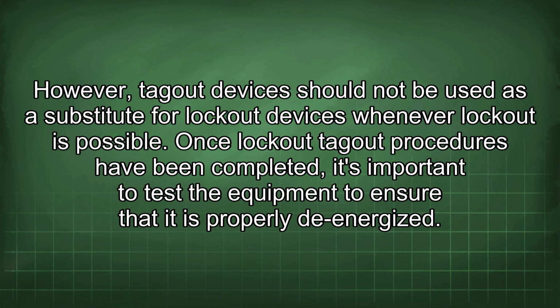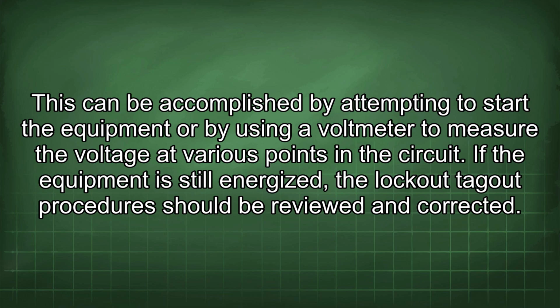Once lockout tagout procedures have been completed, it's important to test the equipment to ensure that it is properly de-energized. This can be accomplished by attempting to start the equipment or by using a voltmeter to measure the voltage at various points in the circuit. If the equipment is still energized, the lockout tagout procedures should be reviewed and corrected.